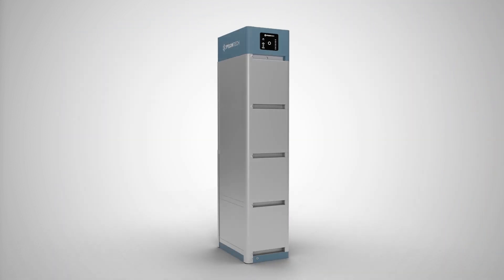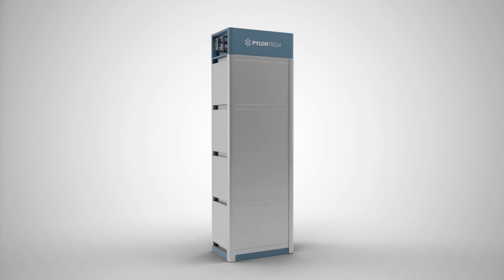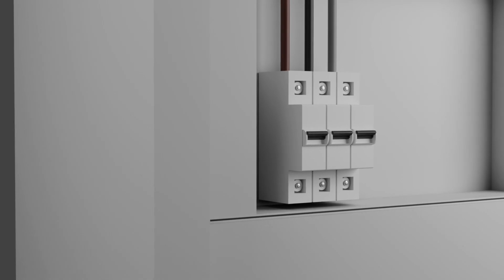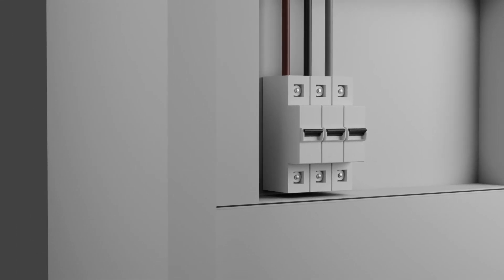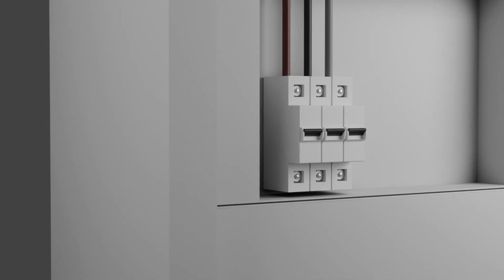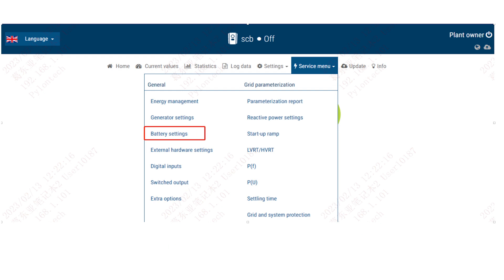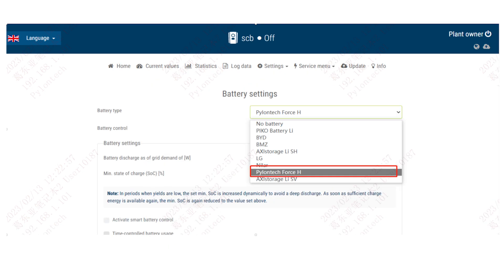The PylonTech battery is immediately ready for use and has been pre-configured for quick commissioning. Start the PlentiCore by switching on the AC fuses. Open the PlentiCore web server via smartphone or tablet and enter the battery activation code if you're integrating a battery into the system for the first time.